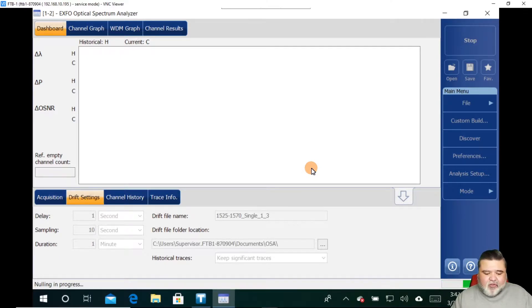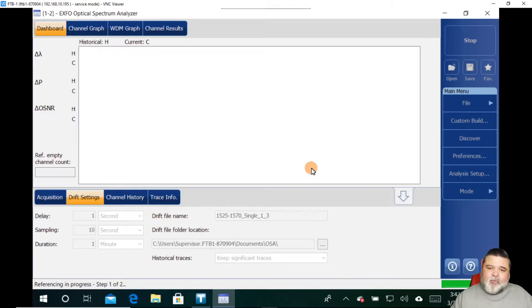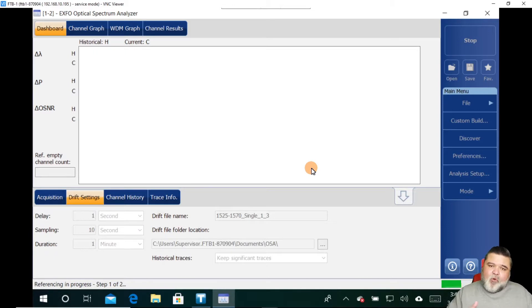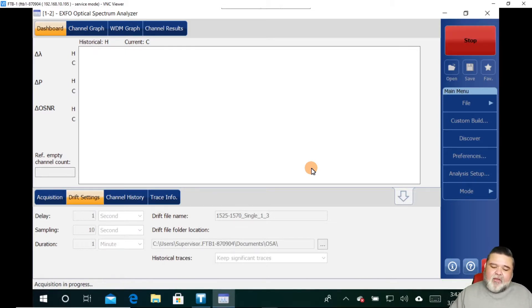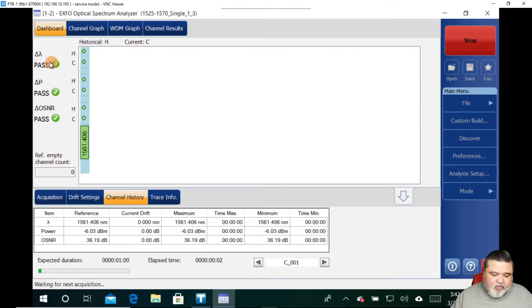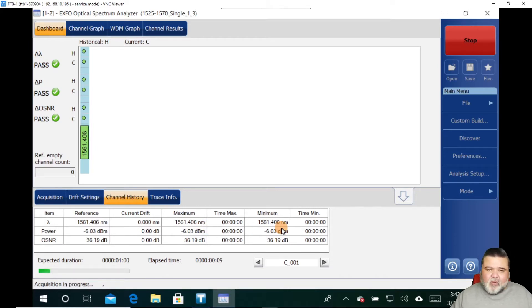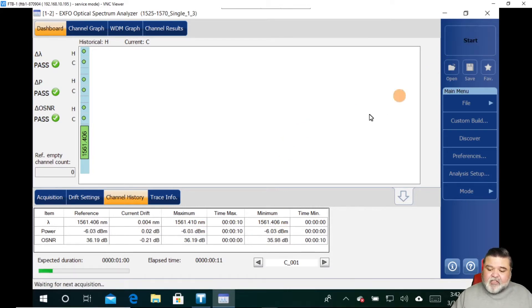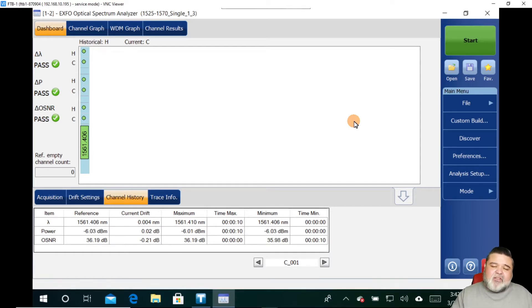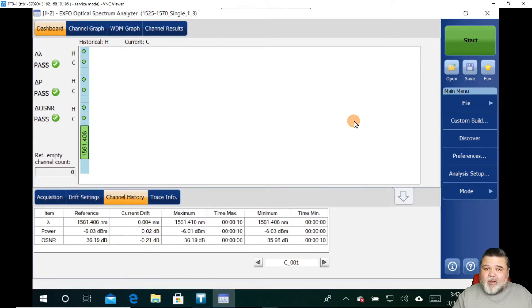Essentially all you do is hit start and then it'll start to do its drift analysis and capture historical data. After the first acquisition is completed and pulled in, then we'll start to see some historical information start to populate as we get more and more sampling in there. Then we can start to see long-term historical information. We can set some pass/fail thresholds, current drift, maximum, those types of things. Essentially, that's how you quickly set up an OSA. It obviously does a lot more than that, but we really just wanted to kind of show you the ease of use.